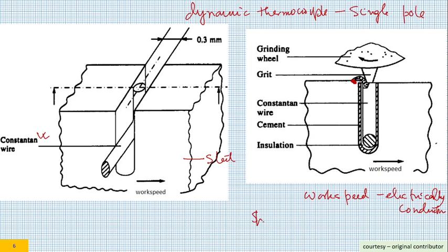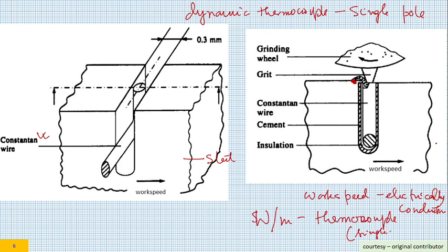When can this technique be applied? When your workpiece is electrically conductive, only then can this technique be applied. Second, your workpiece material and the single pole thermocouple material should generate high enough millivolt or thermo EMF so that it can be measured repeatably and reliably. If it generates very feeble thermo EMF, this technique cannot be used.